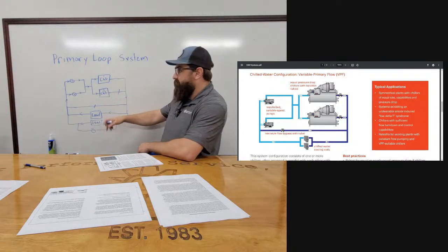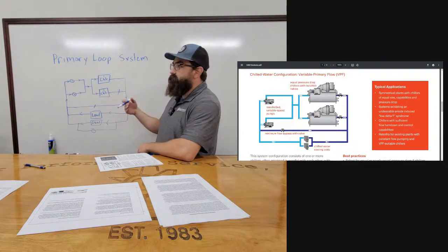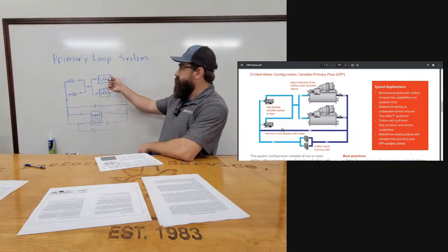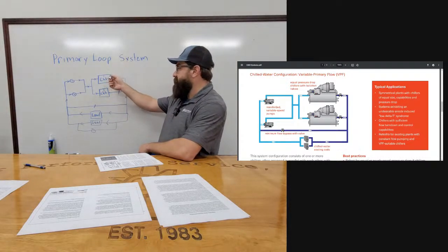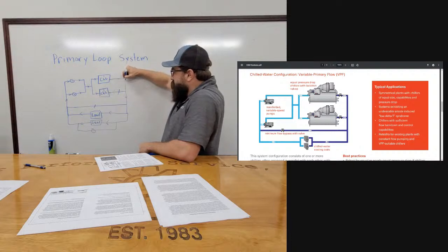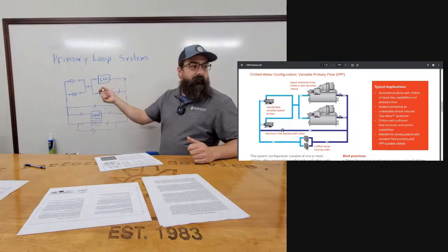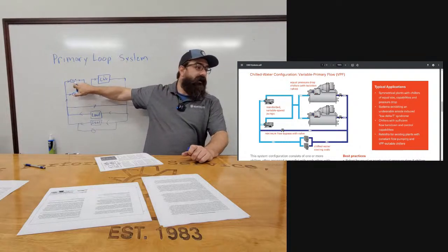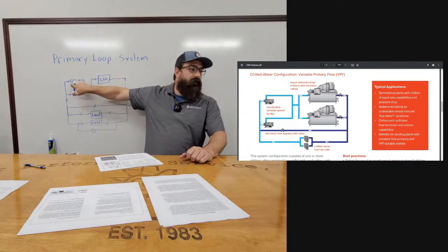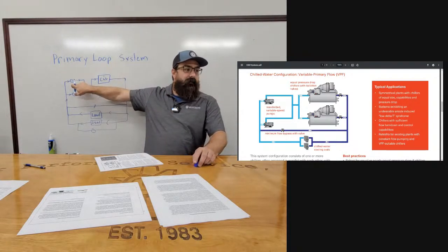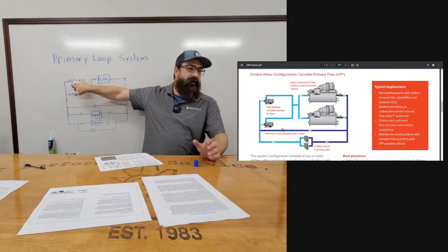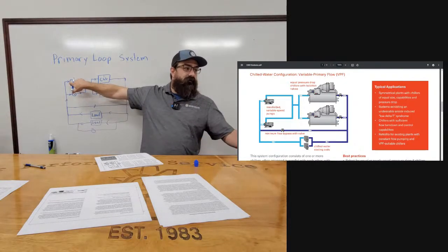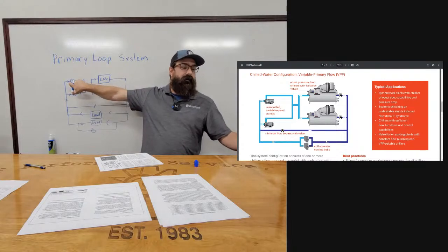If the pump reaches its minimum flow value for the chillers, what needs to be taken into consideration is that you have to maintain a certain amount of flow through the evaporator. So you would have a minimum set in this VFD. That way, no matter what, we never drop below that minimum. It can be programmed in the system, but I prefer to put it in the VFD. That way, even if the system were to call for less flow, it just cannot do it.